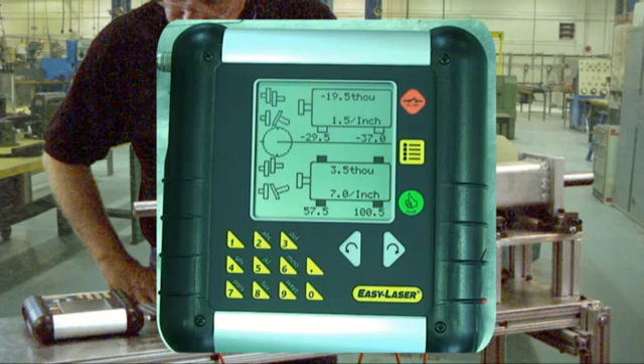Now in the lower horizontal part of the screen the first number is 3.5 thou. This is the amount of offset. The angular misalignment is 7 thou per inch. Both results are measured at the coupling in the horizontal plane.